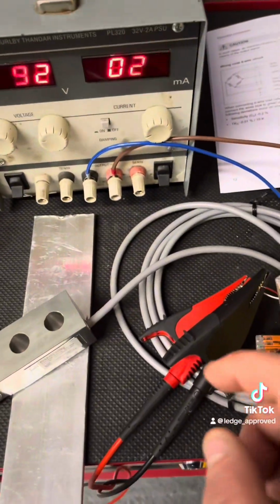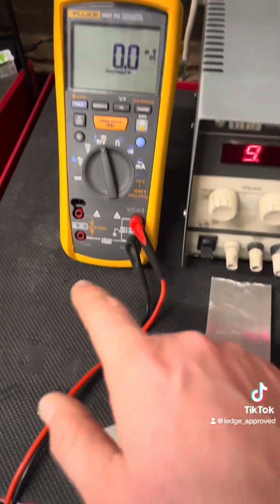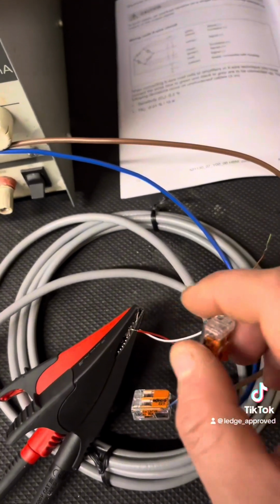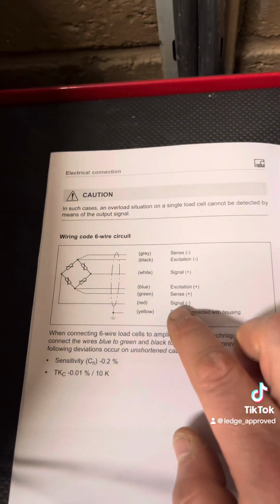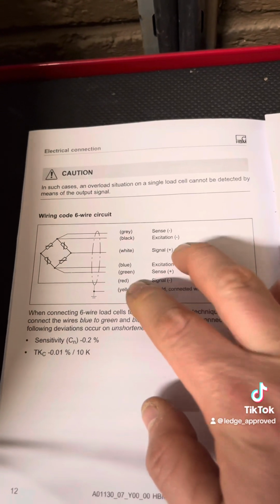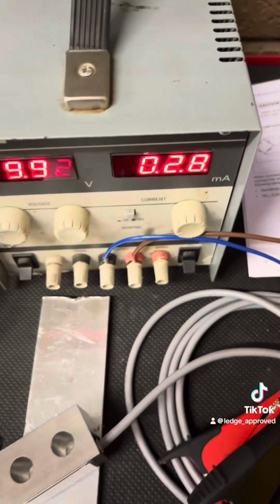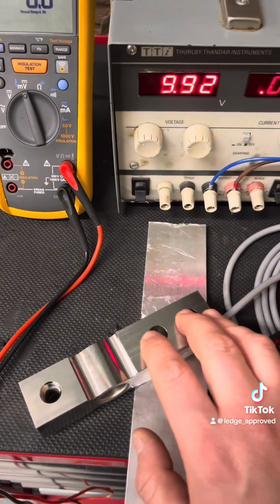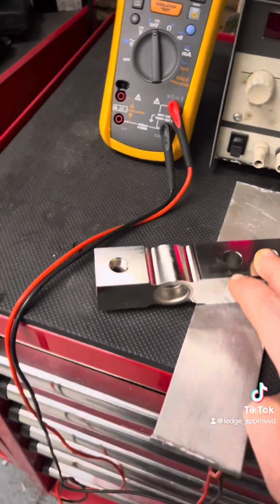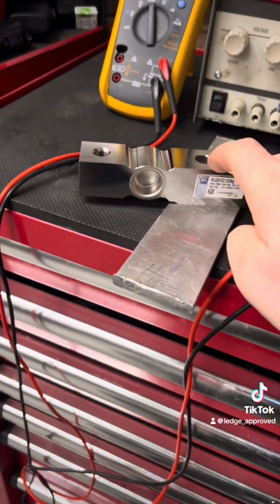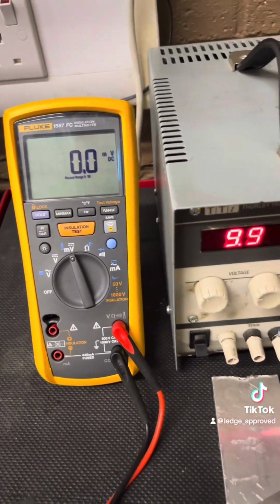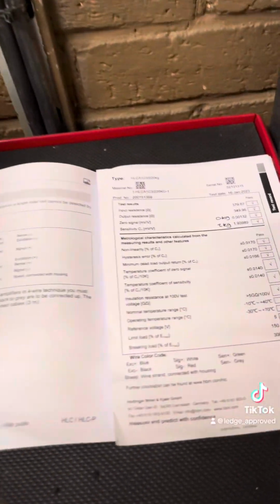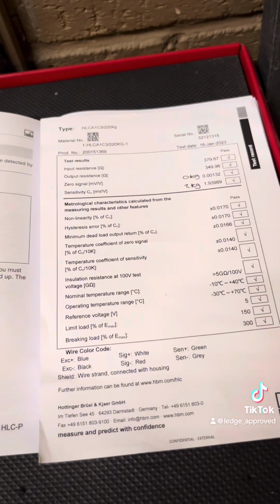So what we're going to do first is a zero test. So here what we want to be seeing is the millivolt output of when it's actually got no load on it at all, to make sure it's to the calibration sheet. So what you can see is I've raised it from the workbench. Now I've got my leads going out to the output. And as you can see, 0 volts. And that's what I calibrated at.